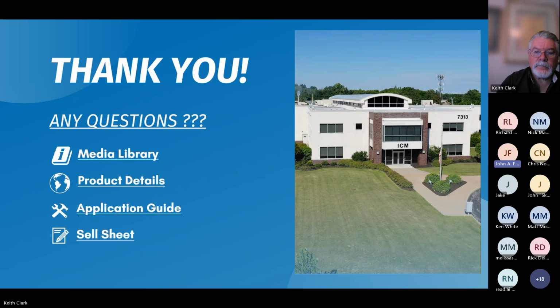The 517 is a little more popular because it can be wired for both 120 and 240. Right now we're marketing the 518 for the split phase, which is 240, because that's all you're going to need it for. People that are going to buy the 518, why wouldn't you put it whole house, put it on the main disconnect coming in on the mains, and then you protect your whole panel. So it's just a different market, maybe more of the industrial electrical market, or if somebody's building a new home, they could put the 518 on, because they haven't put power to the building yet.